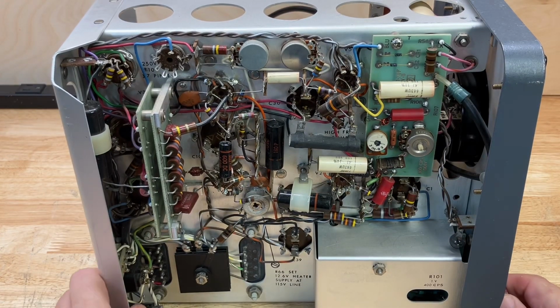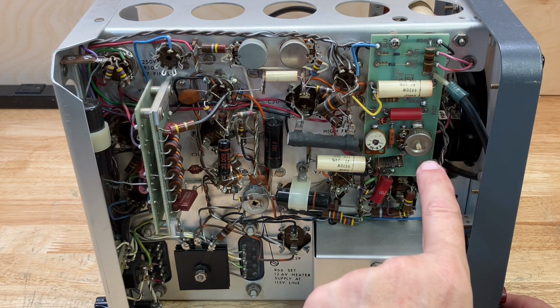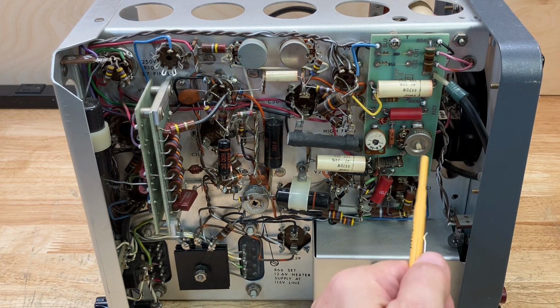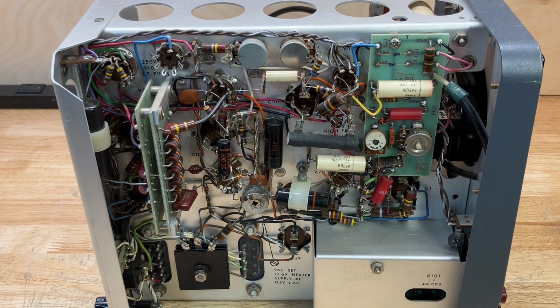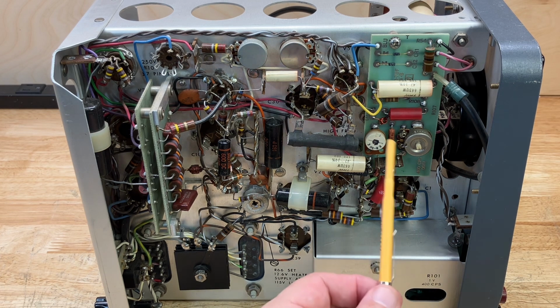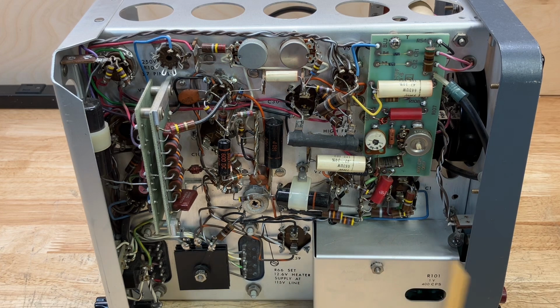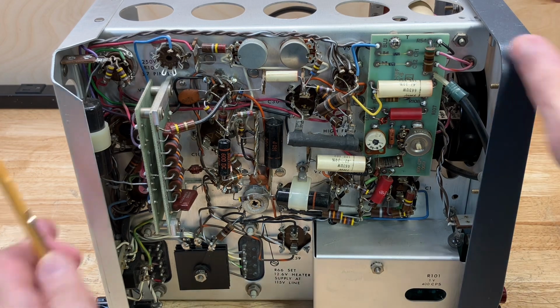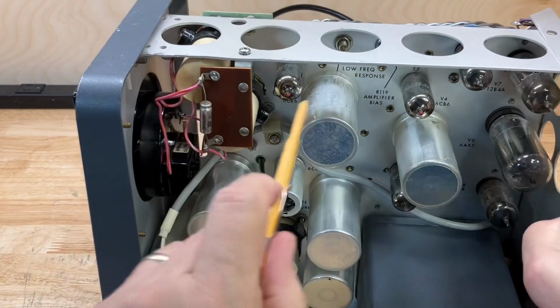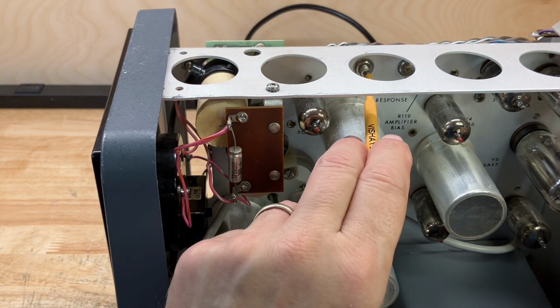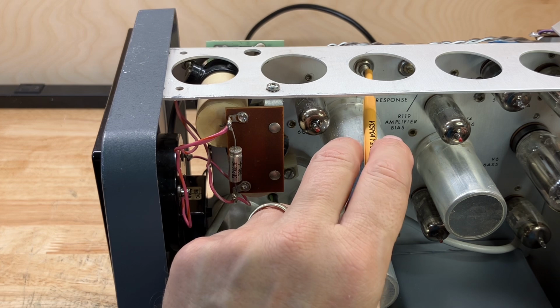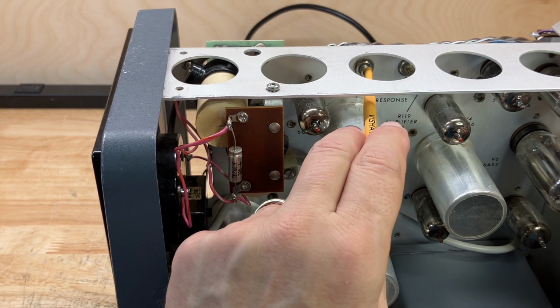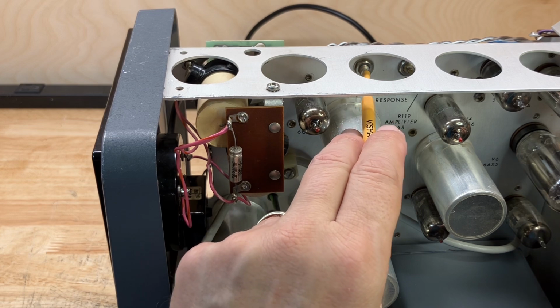We apply 1 millivolt at 400 hertz and adjust this pot right here for the basic to make it read 1 millivolt at 400 hertz. We change the frequency to 4 megahertz and adjust the capacitor to compensate for the 4 megahertz to make the instrument read at 4 megahertz. We also come down here and adjust this pot on this side, the low frequency response, for the correct response at 10 or 20 hertz on the 1 millivolt range. So we have an input of 10 or 20 hertz, and we adjust the low frequency response with that pot.